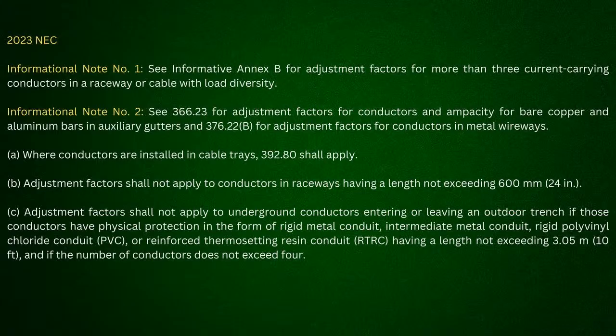induction on our conductors. And if you look at the last sentence that goes with that 392.80(A)(1), listen to what it says. Everybody listen to what I'm about to say. Adjustment factors shall be limited to the number of current carrying conductors in the cable and not to the number of conductors in the cable tray. Yeah. I mean, that can't be any more explicit. And that's why I'm saying the same thing.